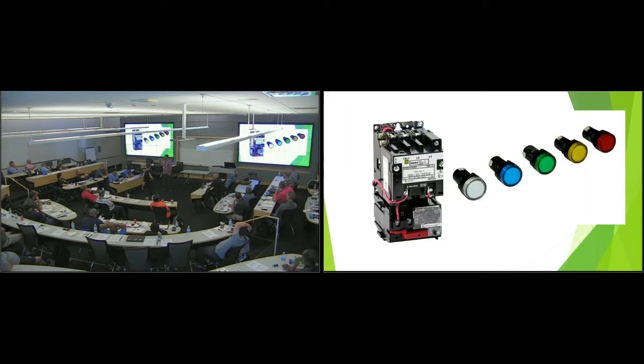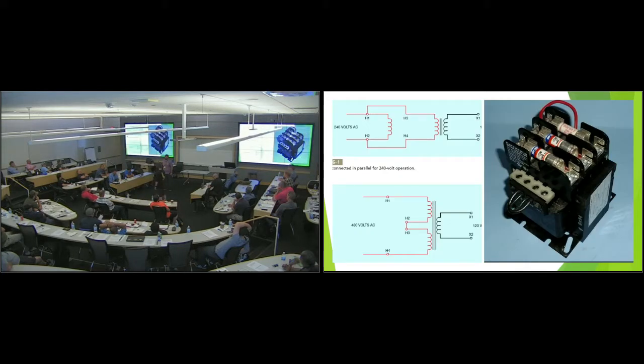Before we move too far away from control transformers, I want everyone to keep in mind that just because you throw the disconnect switch, that does not mean the control system is dead. Sometimes your controls are fed from a different source. You should always check that before you just assume.